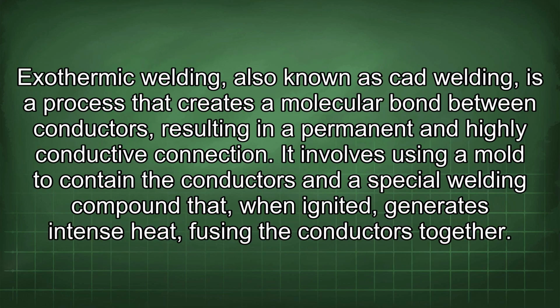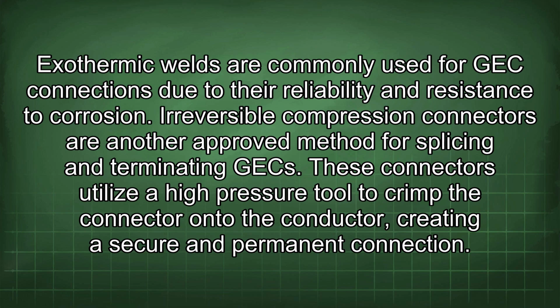Exothermic welding, also known as cadwelding, is a process that creates a molecular bond between conductors, resulting in a permanent and highly conductive connection. It involves using a mold to contain the conductors and a special welding compound that, when ignited, generates intense heat, fusing the conductors together. Exothermic welds are commonly used for GEC connections due to their reliability and resistance to corrosion.